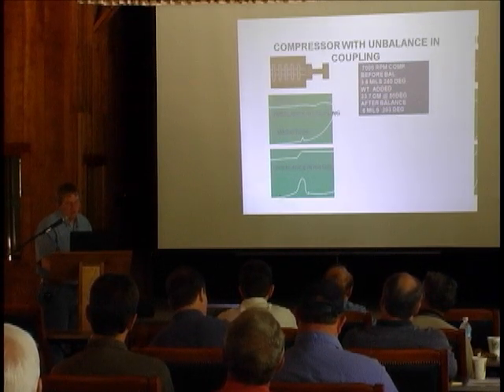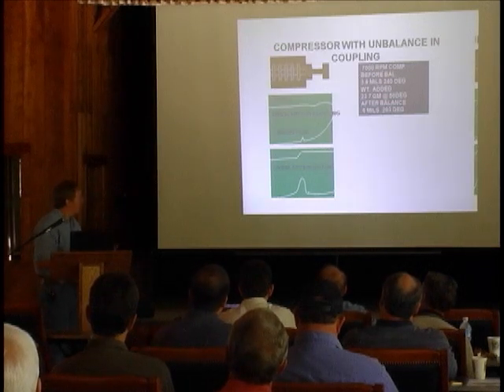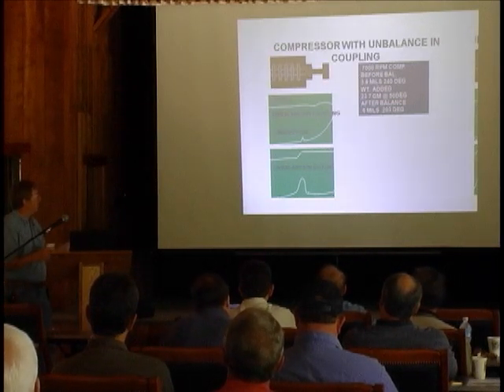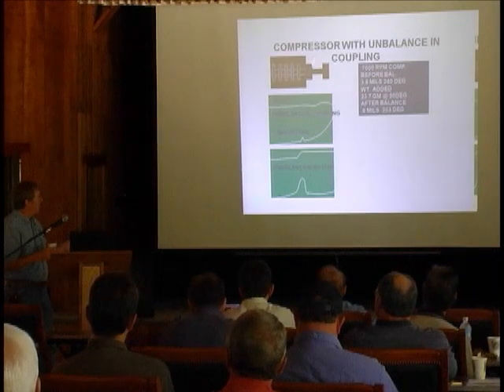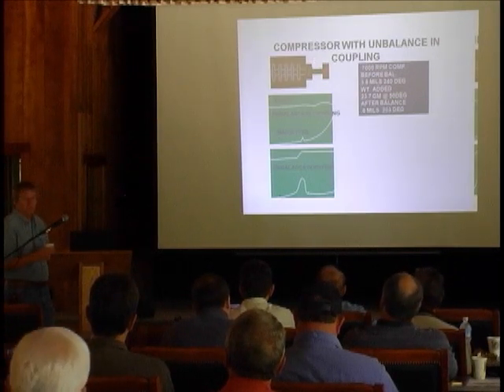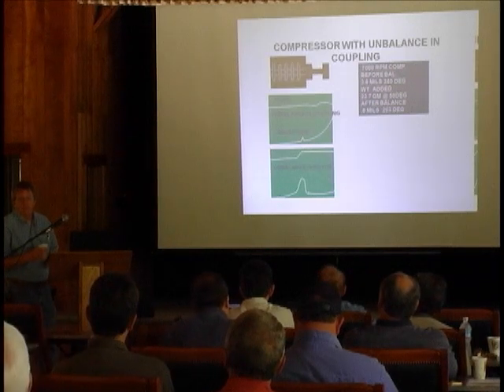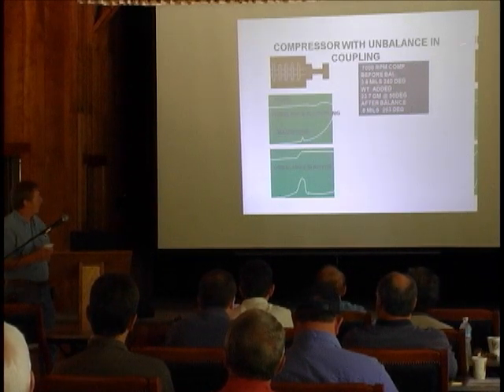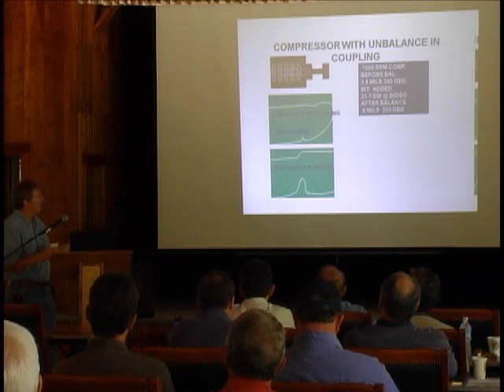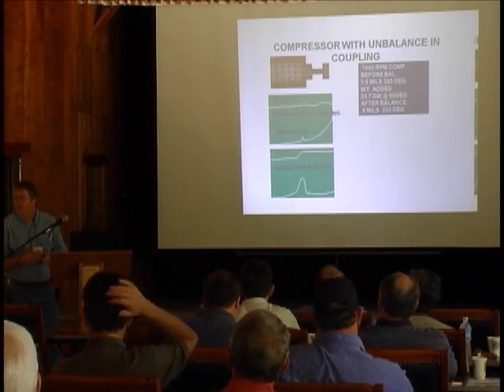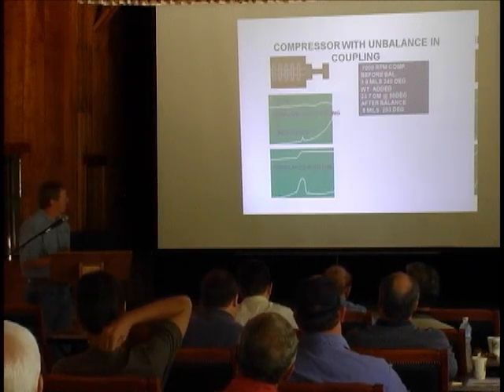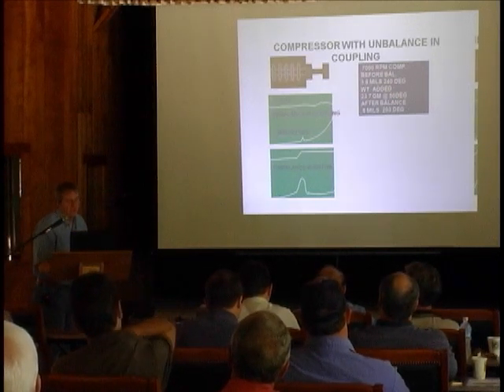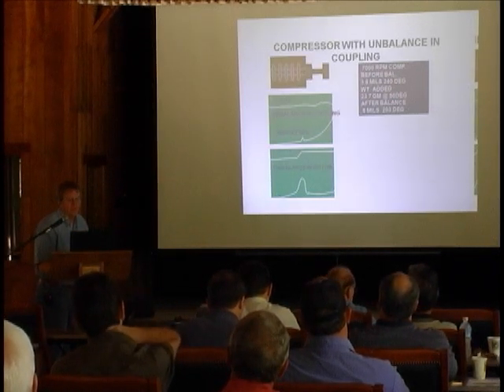thing back together. Because if you take a high-speed compressor like this, turning 15,000 RPM, and you get unbalance in the coupling, which is an overhung mass, they're extremely sensitive to this. And then you put in the fact that your prox probes are right here. Those prox probes are going to be reading that, and you have to be very, very careful in that situation. I've done a number of these. I had one where I only added 4 grams.